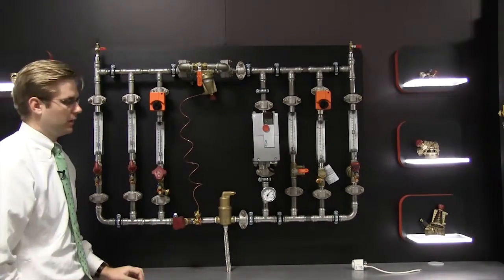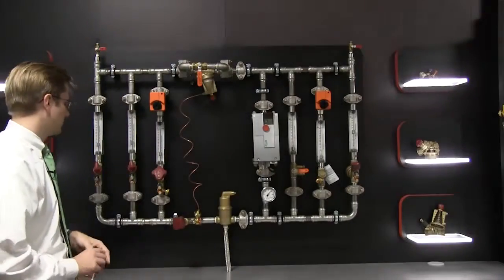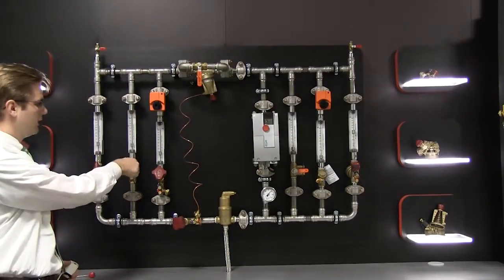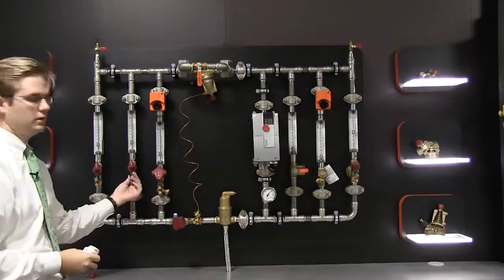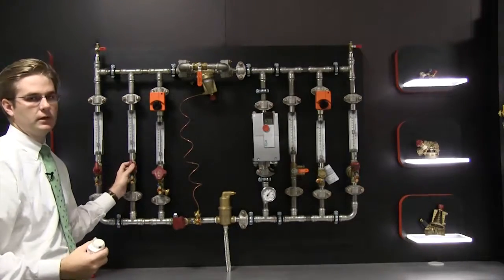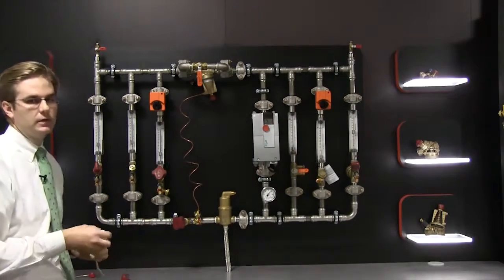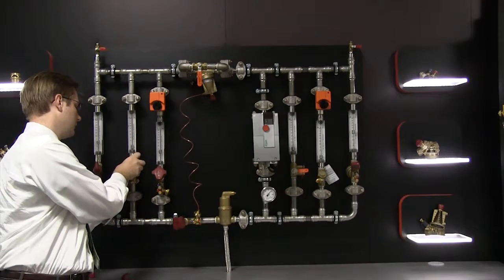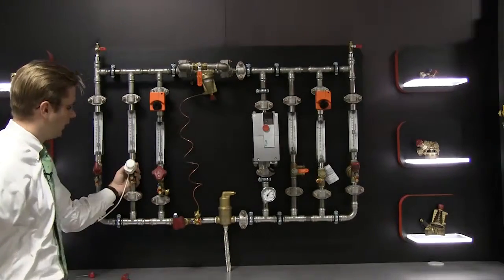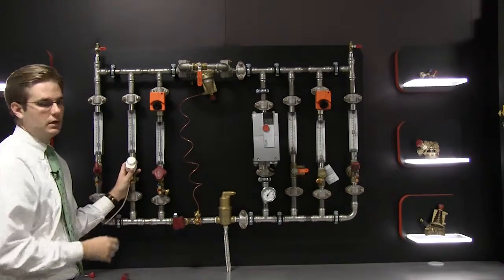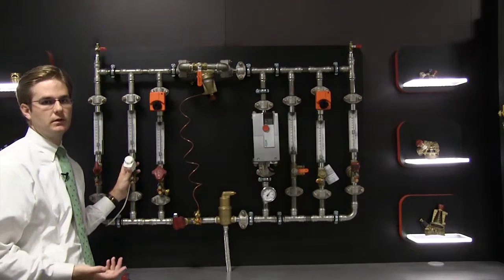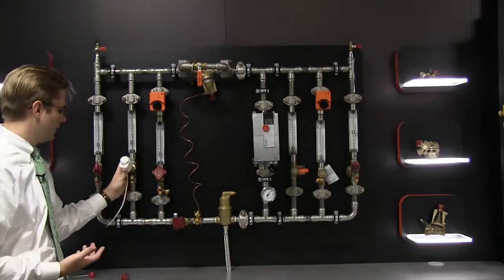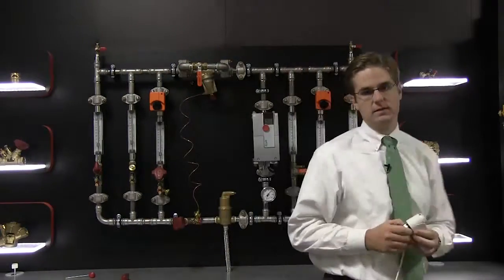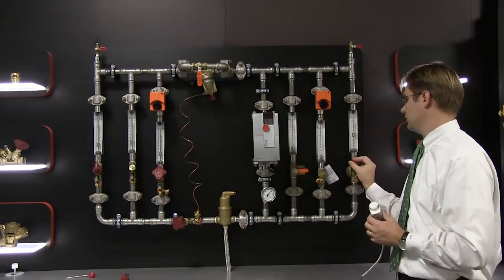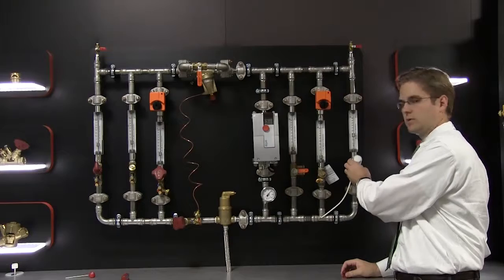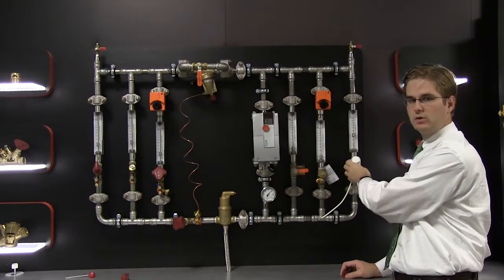The other new product that we have is our TBV CM valve, which is over here. This valve is similar to a manual valve. You can set it, you can read the flow rate, but once you're done commissioning the building, you can take the handle off and you can attach a modulating control valve actuator. And this now turns that manual balancing valve into a control valve. Same as any other 0 to 10, 2 to 10 modulating control valve that you would see out there. It has the same function on the TBV CMP. I can set the flow rate, then I can take the knob off and install an actuator to turn this balancing valve into a control valve.